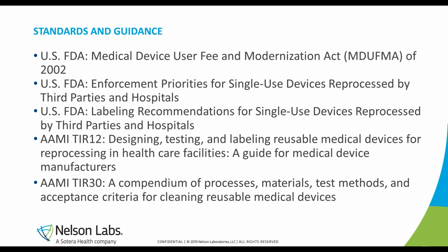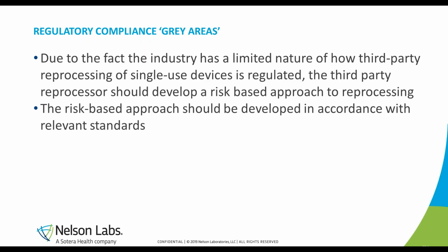Additional standards commonly used for third-party reprocessing are the technical information reports developed for reusable devices. TIR 12 and TIR 30 provide guidance for cleaning or reprocessing validation for reusable medical devices and can be applied to single-use device reprocessing as well. Even with these recommended standards and guidance, there still remains a lack of detailed regulatory guidance, requirements, and specifications for the reprocessing of single-use devices.